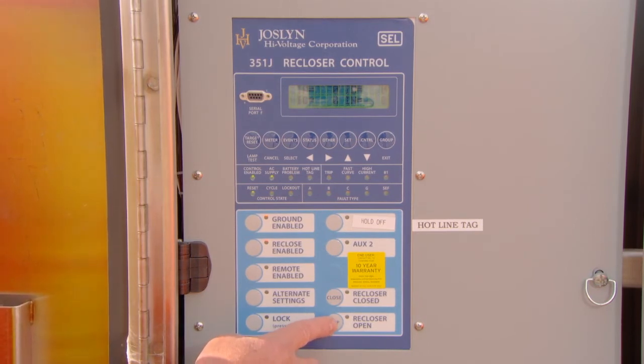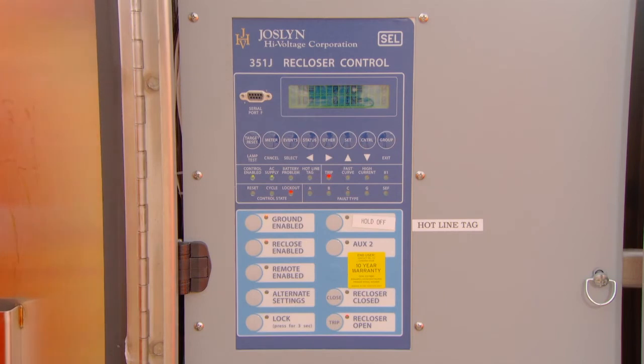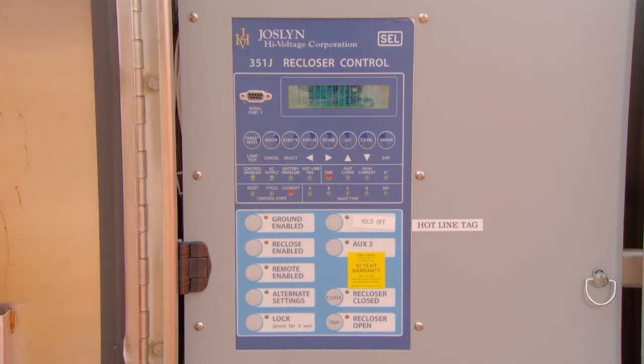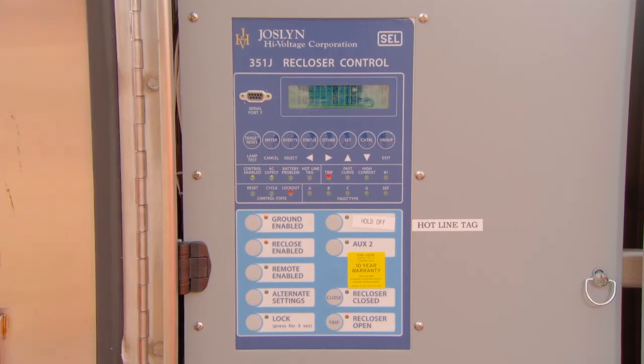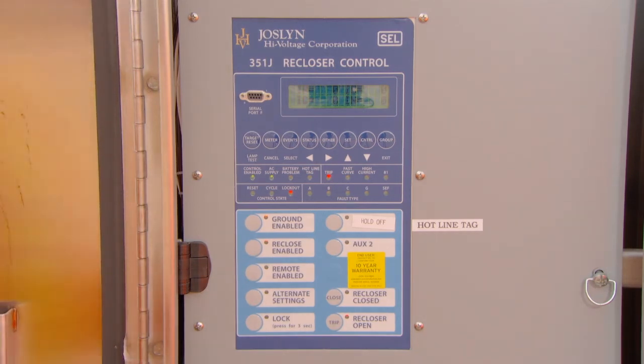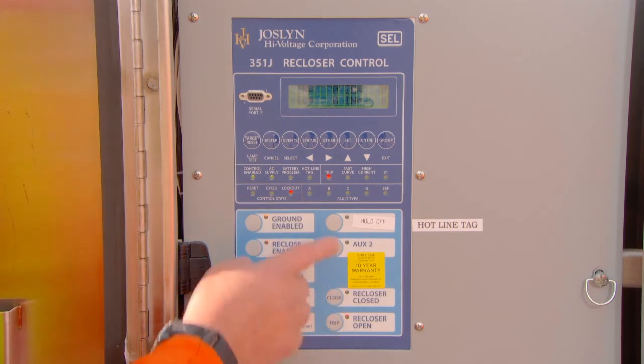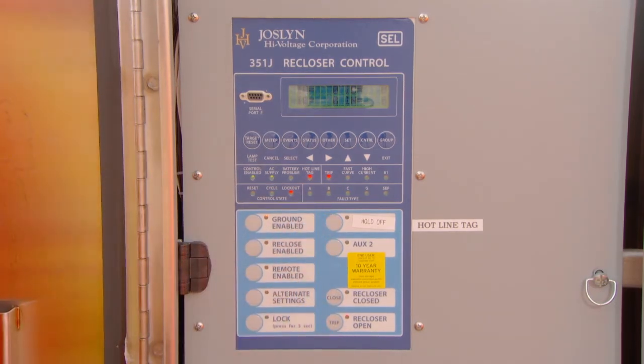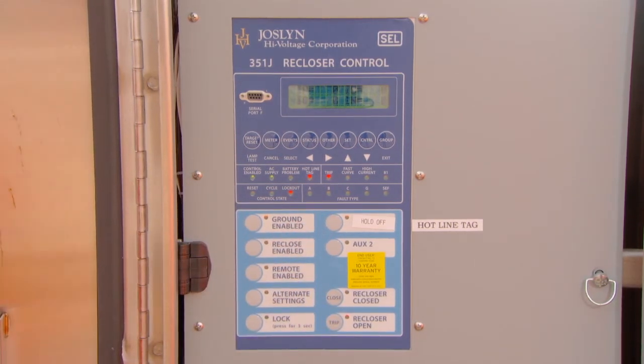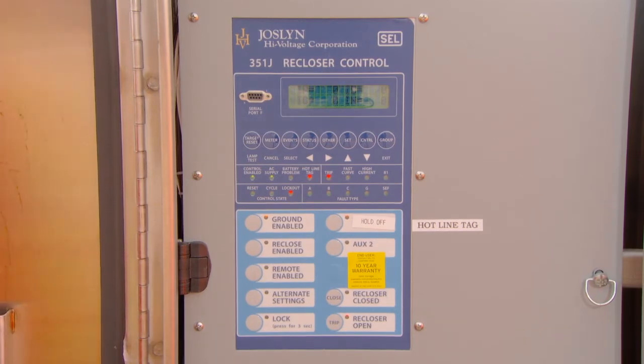To trip the unit, press the trip button. This will instantly trip the unit open, and the open indicator LED will now turn red. The trip LED will also illuminate red. It is possible to set the hold off with the contacts open. However, the unit cannot be closed with a hotline tag or hold off in place. Pressing the button in this state will not close the unit. If a hotline tag is active, it must be removed before the unit can be closed.